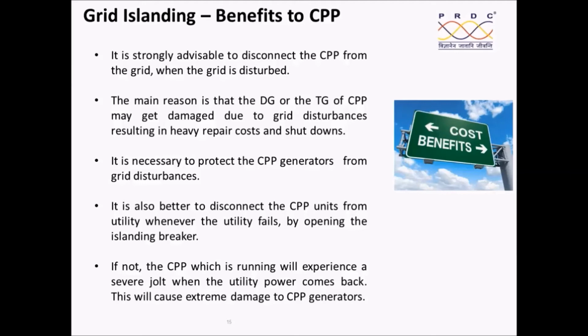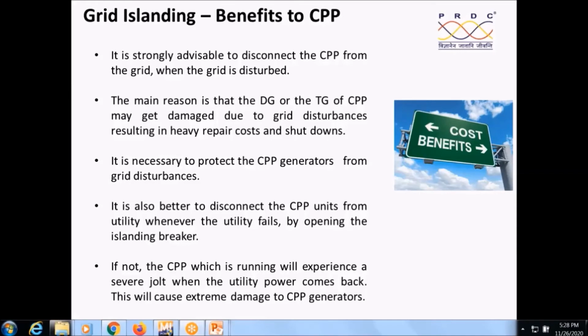We need to protect the CPP generator from the grid disturbances. There can be a prolonged under voltage, prolonged over voltage, prolonged under frequency. We need to ensure that the captive power plant generators are protected from these disturbances. There is a complete insulation of the disturbances to these generators. And whenever the utility fails, by opening the islanding breaker we can still continue to have the power supply. Assume that the grid line has tripped. Then it may so happen that the CPP along with its own load will be able to survive.